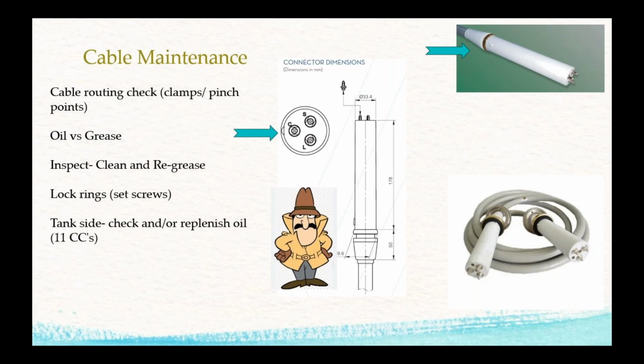The well's designed with a slot that key fits into, and just for our troubleshooting purposes, the reason it's even up here is that it designates where the common wire is. You might see that again. The key is the common wire, and then we have our small and our large filament on our cathode side, and then on the anode side, what they do is short all the pins together so we have full power on the anode, but on the cathode side, you need to differentiate between small and large filaments, so we have the 3 distinct pins. The key is the common if you're ohming out the cable.